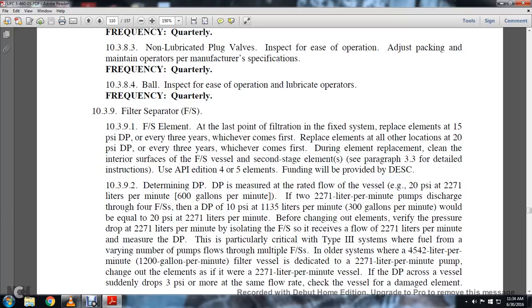Isolate the filter separator so it receives 600 gallons per minute and measure the DP. This is particularly critical for Type 3 systems, where fuel from the pumps flows through multiple filter separators, in order to reach system flows of 4,542 liters per minute or 1,200 gallons per minute. Each filter separator is sized at 2,271 liters per minute per pump. Change the elements in the filter separator at 2,271 liters or 600 gallons a minute per vessel.